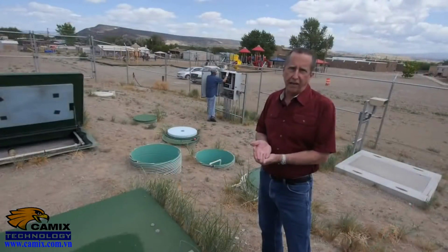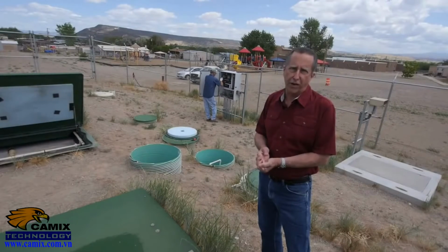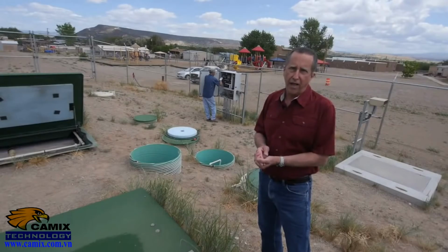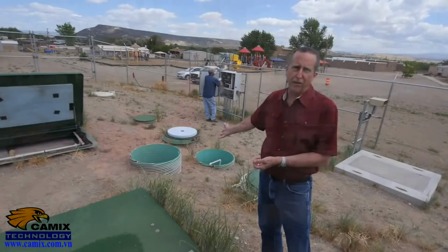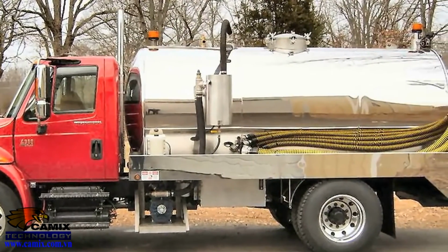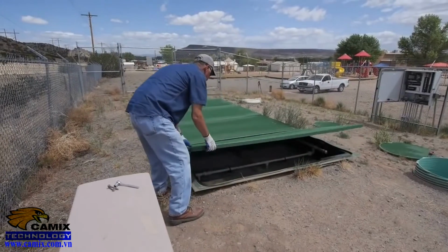Anything that can settle out of the raw sewage will settle. Anything that can float, like oils and greases, will float. Any kind of trash can be separated out. The primary step has to be maintained. It can be pumped out with a pump truck every 6 months to a year to remove any accumulated solids. And then it flows over to the secondary process.